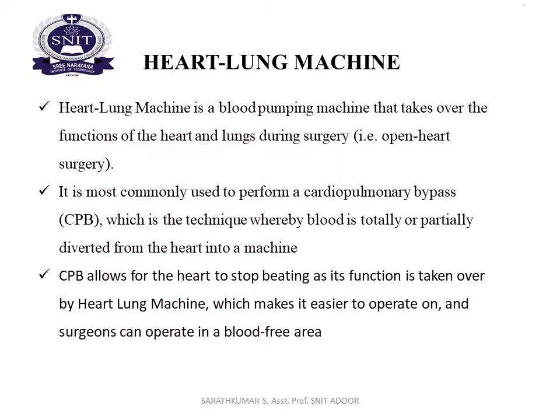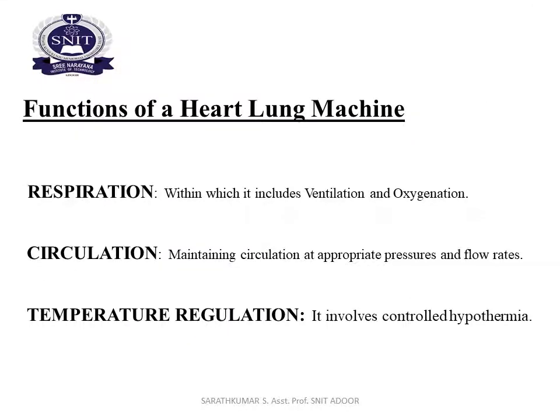It is most commonly used to perform cardiopulmonary bypass (CPB), which is a technique whereby blood is totally or partially diverted from the heart into a machine. CPB allows the heart to stop beating as its function is taken over by the heart lung machine, which makes it easier to operate. Surgeons can then operate in a blood-free area.